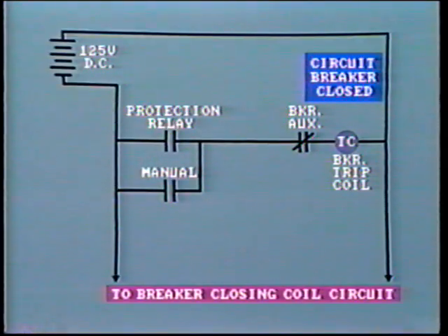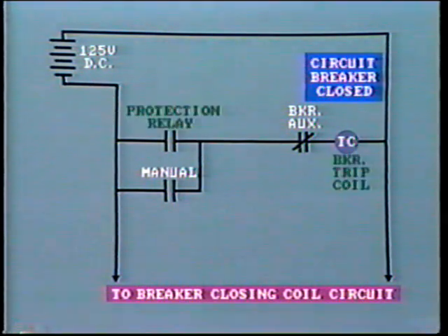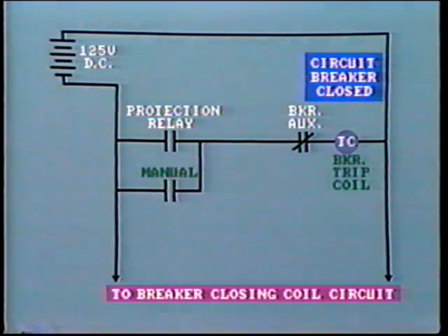Let's look at this tripping circuit. A 125-volt DC system is provided for operation of the breakers. The circuit breaker closing and tripping coils are energized by 125-volt DC from the station battery, as this provides a continuous and reliable power supply. When the circuit breaker is closed, the elementary tripping circuit will look like this. These auxiliary contacts are closed because the breaker is closed, but the tripping coil will not be energized until either 1, the protective relay contacts close, or 2, the manual switching contacts are operated.